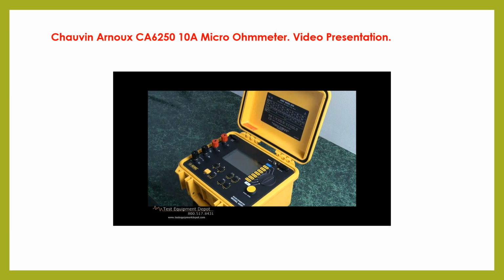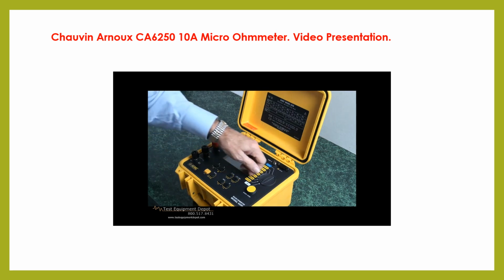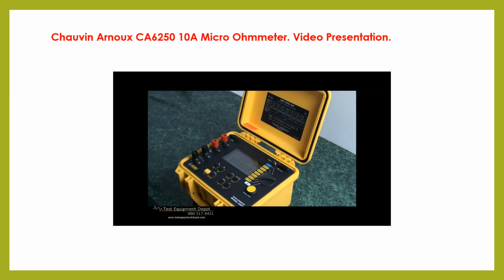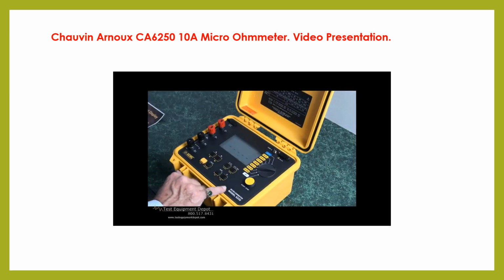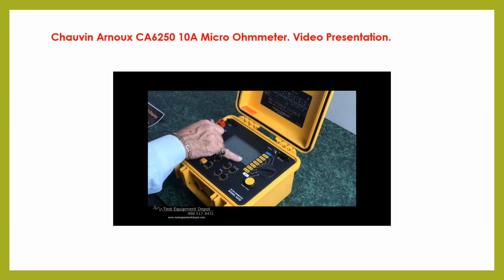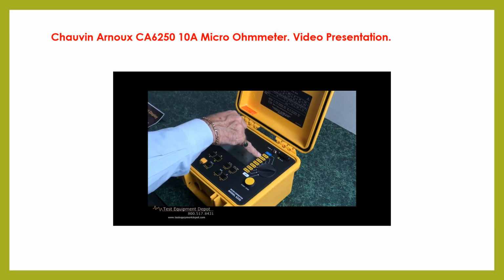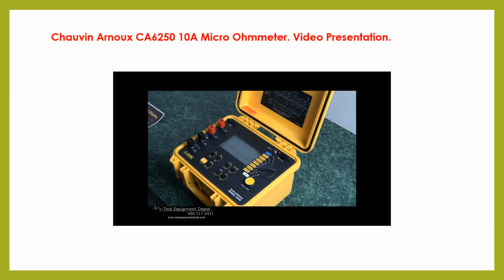It has a large backlit display, and we can show that by turning it on, selecting any channel, and selecting the light to backlight it. Now, first we see the multiple scale selection. Starting with 1 milliamp, we can increase it to 10 milliamps, 100 milliamps, 1 amp, 10 amp, and again 10 amp. With each incremental step, not only are we increasing the current that's going to be driven through the test specimen, we also will be increasing the accuracy, or the number of decimal places that will be displayed.